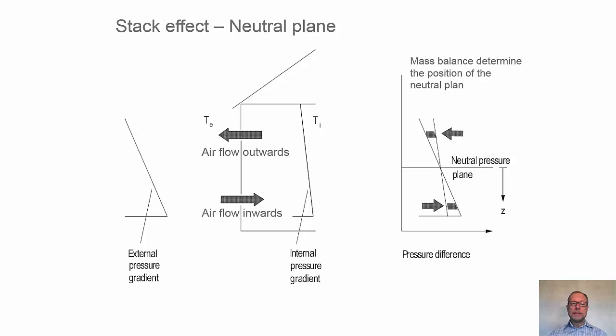But since we must have an air balance, a mass balance, air that flows in due to pressure difference and air that flows outwards due to pressure difference, there must be equal amounts flowing in and out. And then a neutral pressure plane will be developed where we have the same pressure inside and outside.